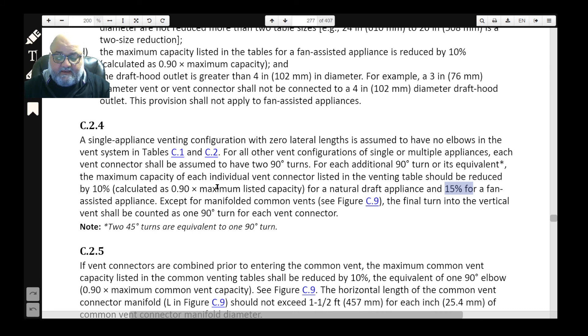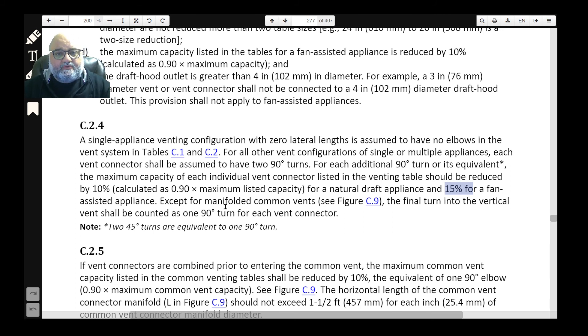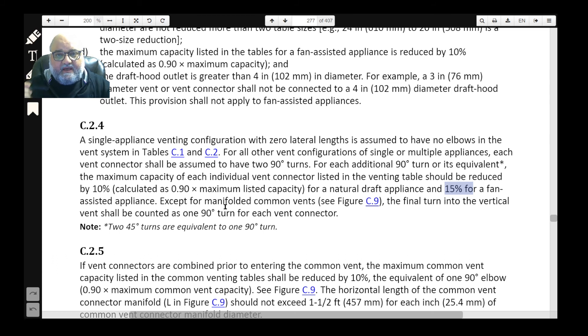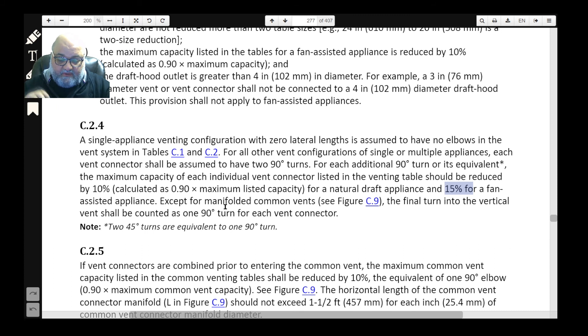However — and this is why I call it the extra elbow GVR — for each additional 90-degree turn beyond those two, the maximum capacity of each individual vent connector listed in the venting table must be reduced by 10% or 15%. Every extra elbow represents significant resistance to flow, so we reduce capacity to account for that extra resistance.